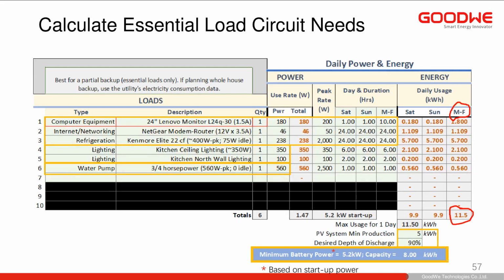If I think that I have great transfer time because I have an embedded ATS inside my ESS to an essential loads panel, then I have quick transfer time. I don't need to be able to back up all 5.2 kilowatts. I can just get something that's maybe 2 kilowatts of power. Now, this is obviously a small system, but it's just an example. However, if I think I have a longer transfer time, then I want to get an ESS that can handle 5.2 kilowatts at least of backup power.